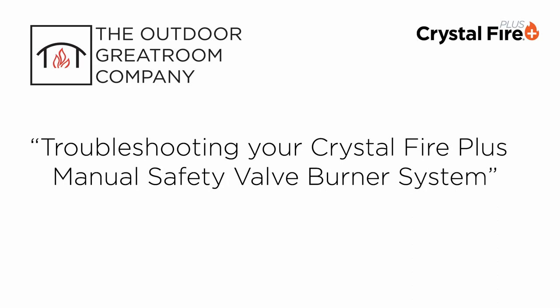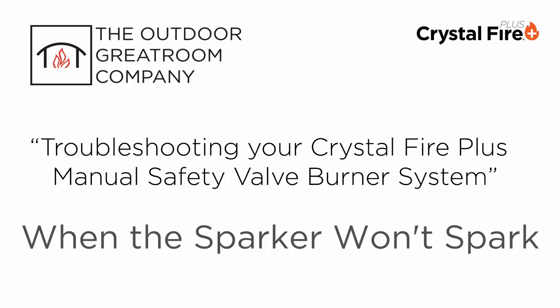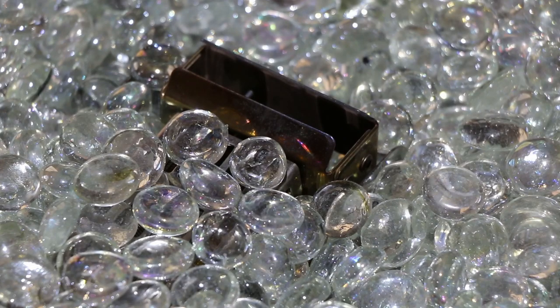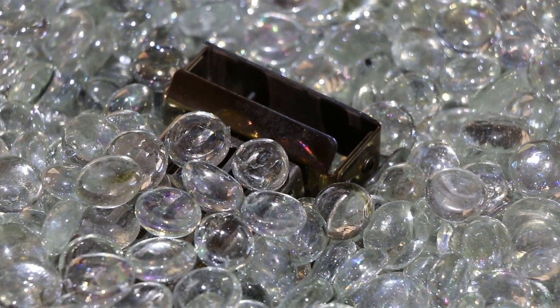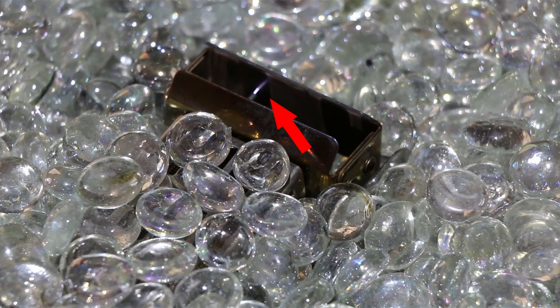This video will go through the basic troubleshooting of your Crystal Fire Plus manual safety valve burner system when you cannot get the sparker to spark. When depressing the sparker button on the control panel, you should get a spark on top of the burner between the tip of the igniter and the steel wind guard as shown here.